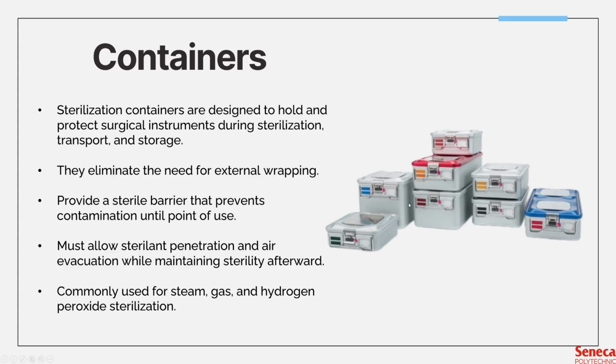So sterilization containers are designed to hold and protect surgical instruments through the entire sterilization, transport, and storage process. They eliminate the need for external wraps, which helps reduce waste and improve workflow. External wraps include SMS wraps, reusable and disposable.